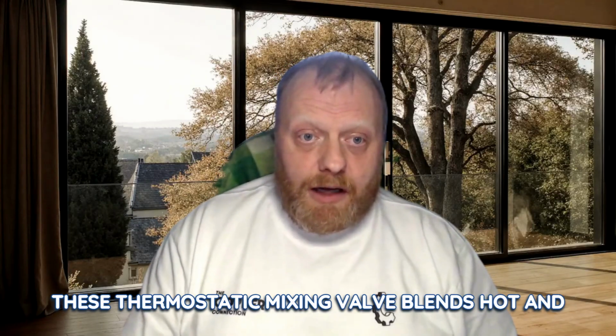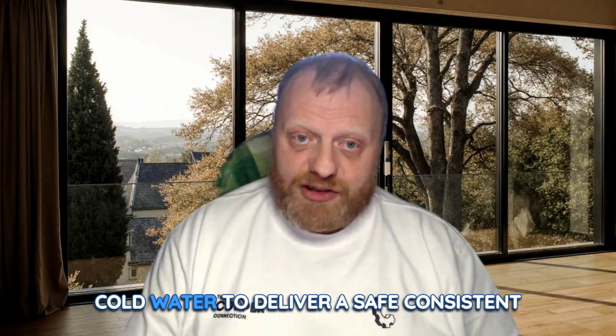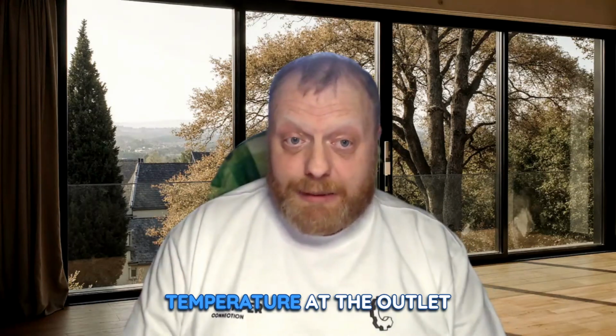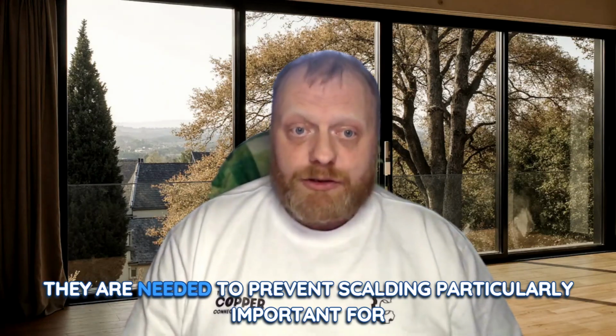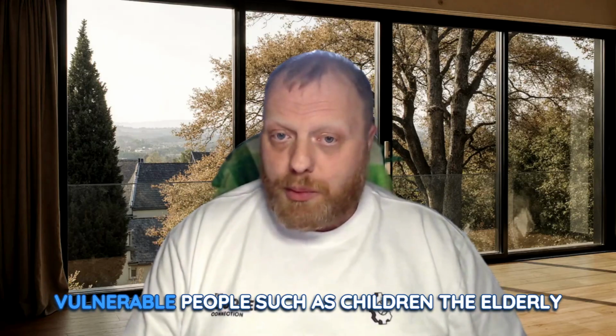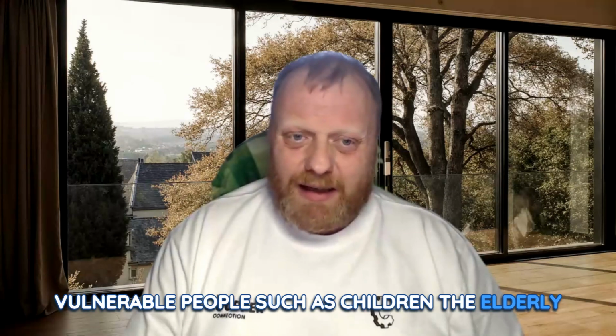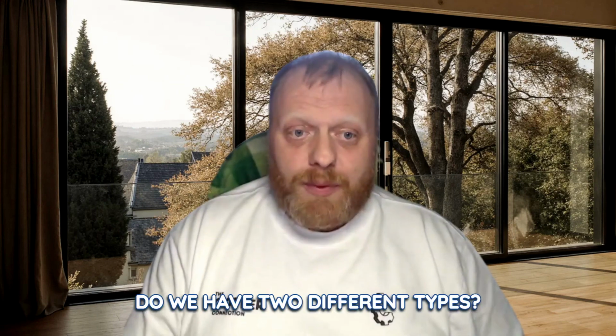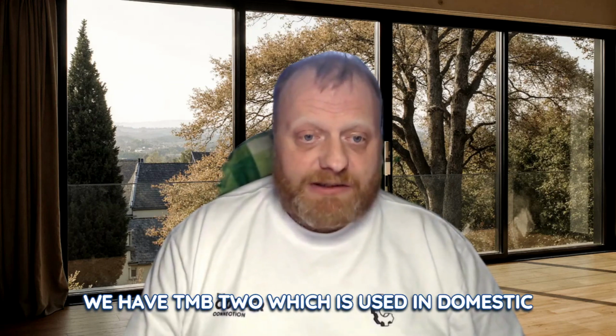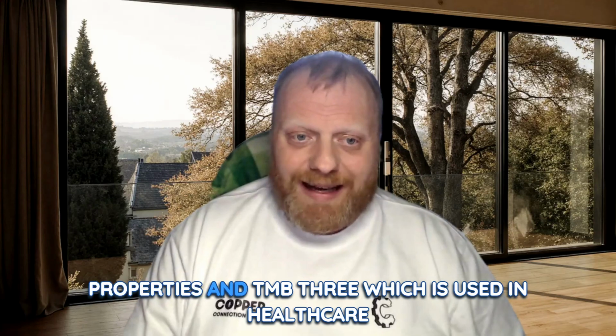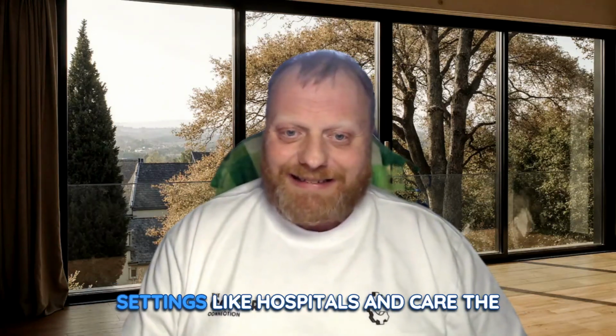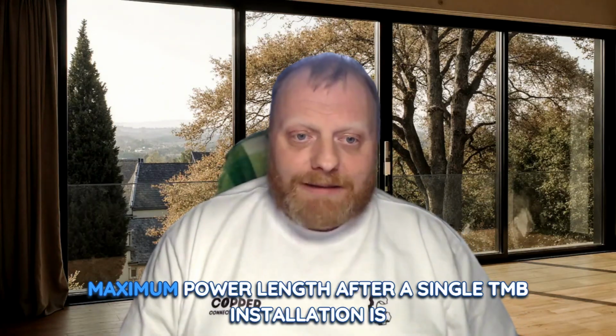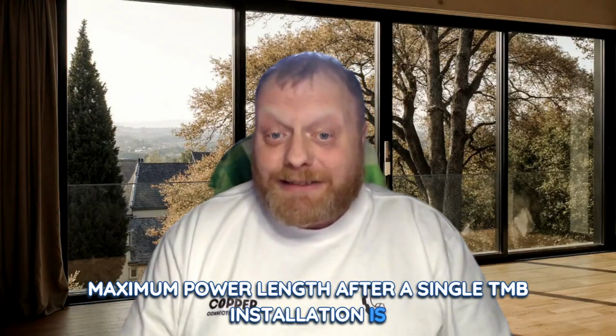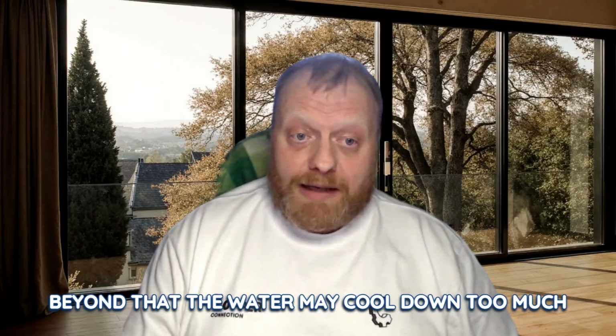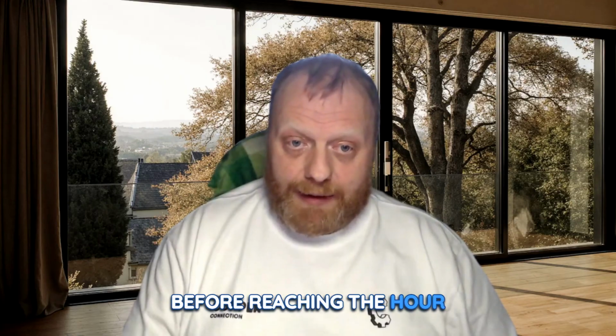Okay, so now let's take a look at thermostatic mixing valves, TMVs. A thermostatic mixing valve blends hot and cold water to deliver a safe, consistent temperature at the outlet. They are used to prevent scalding, particularly important for vulnerable people, such as children, the elderly, and those in a care setting. Then we have 2 different types of TMVs. We have TMV2, which is used in domestic properties, and TMV3, which is used in healthcare settings, like hospitals and care homes. The maximum pipe length after a single TMV installation is 2 metres. Beyond that, the water may cool down too much before reaching the outlet.